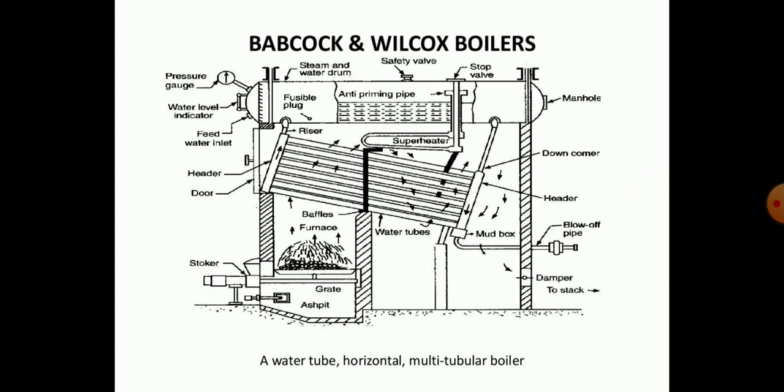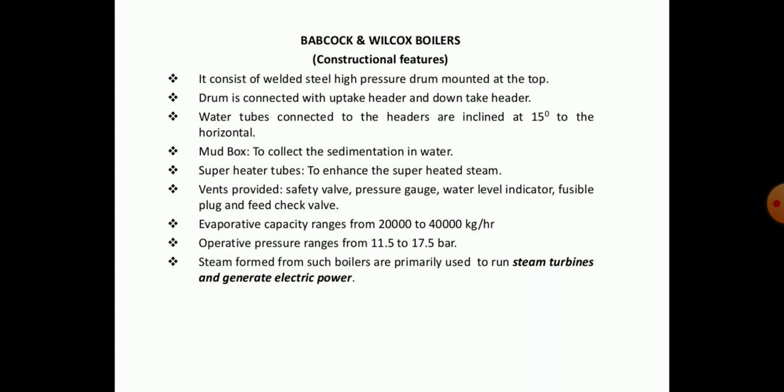Babcock and Wilcox boilers fall into the category of water tube boilers. In its construction, it consists of a welded steel high-pressure drum mounted at the top, connected to uptake and downtake headers. Water tubes connected to the headers are inclined at 15 degrees to horizontal, and a mud box collects sedimentation from the water. Superheater tubes are used to produce superheated steam, while vents are provided for safety valves, pressure gauge, and water level indicator. Its evaporative capacity ranges from 20000 to 40000 kg per hour, with operating pressure ranging from 11.5 to 17.5 bar.